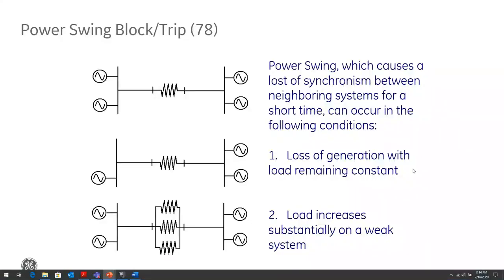A power swing can be seen as a condition when a stable power system loses synchronization for a period of time with the neighboring system, and then later regains synchronization. There are two reasons which can cause this type of power swing. One is when a significant amount of generation instantly becomes much weaker, but the load of the system remains constant. And then the other is if the system is already weak and the load suddenly increases substantially. So the power will start to swing.